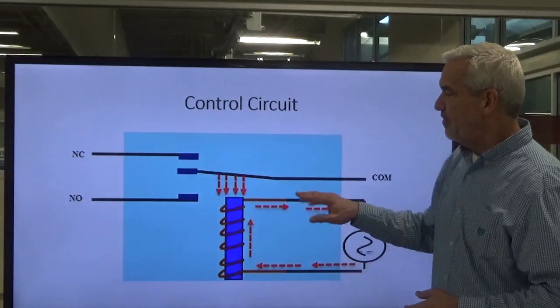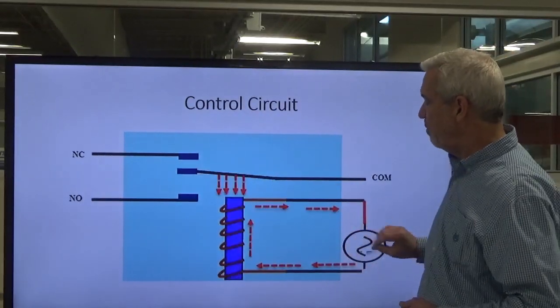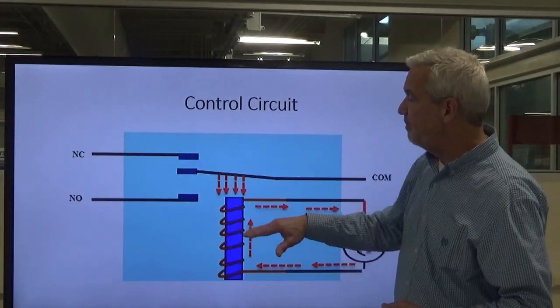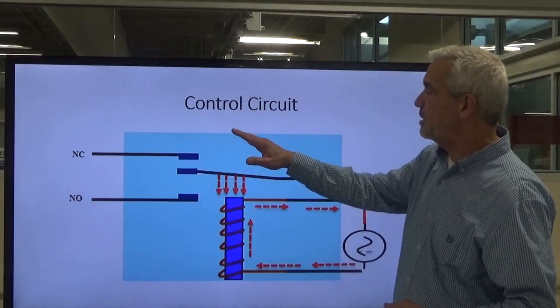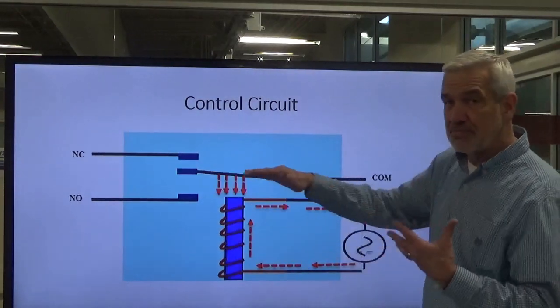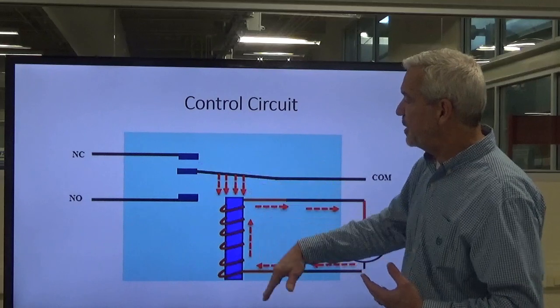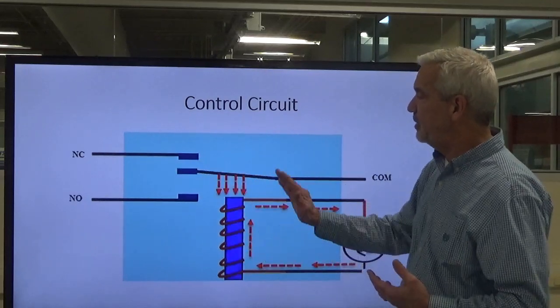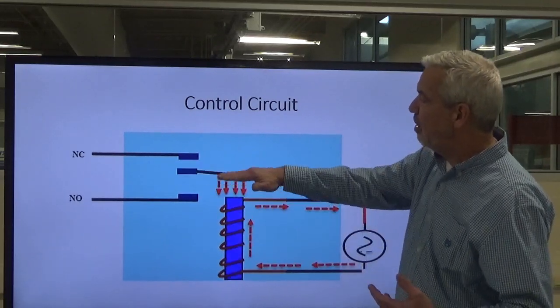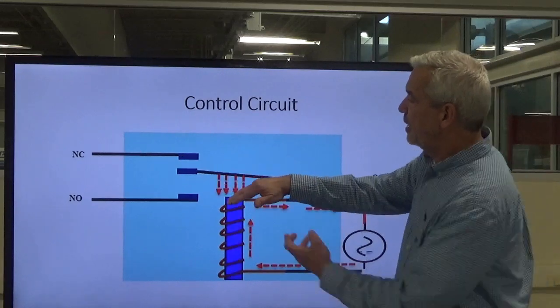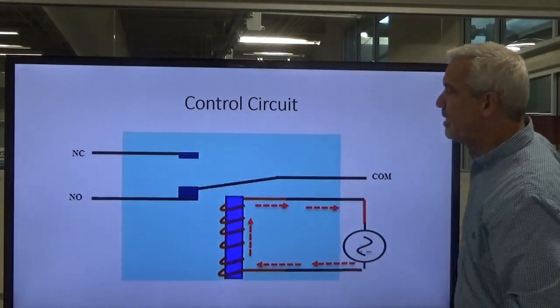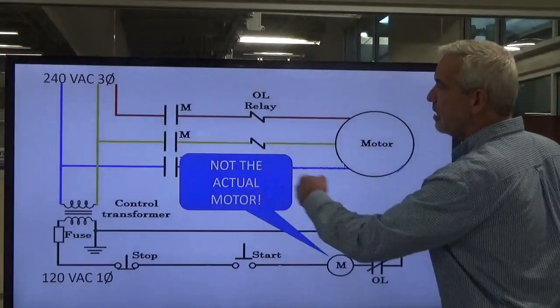Okay, so again, when we shut the current off, the voltage off, a spring pushes these contacts back up, and I wish I could stop this in motion, but I can't. So we're just energizing, de-energizing, energizing, de-energizing, and all it's doing is pulling that armature down here, and these armatures are connected to a set of contacts, okay? Doing the exact same thing here.